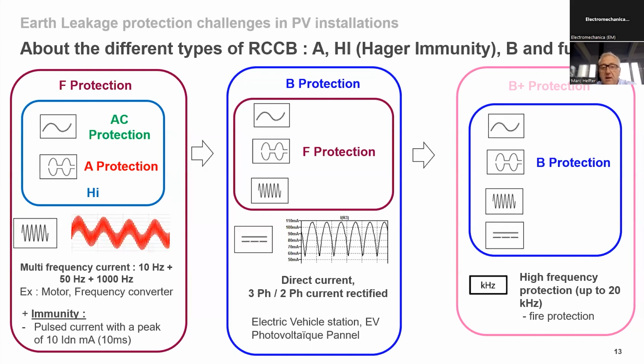We have also the B type. The B type is F-type with direct current. This product is able to detect direct current leakage and to trip. And we have the B plus protection, which is a B type, which is not available today, but that's future, with high frequency protection up to 20 kilohertz, intended for fire protection, the kind of arc fault detection, more or less. So that's what is existing today in the landscape as RCCBs.